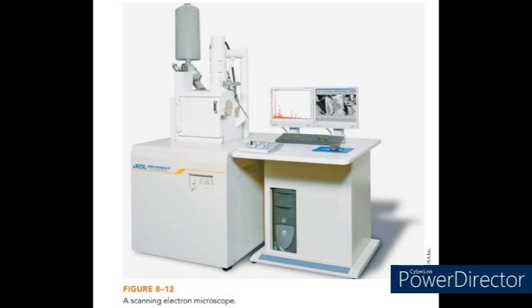Also, 20 to 30% of the primary electrons rebound off the surface. These electrons are known as backscattered electrons. The emitted electrons, both secondary and backscattered, are collected, and the amplified signal is displayed on a monitor. By scanning the primary electron beam across the specimen surface in synchronization with the cathode ray tube, it is possible to convert the emitted electrons into an image of the specimen by display on the cathode ray tube.